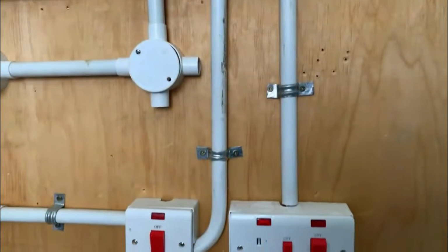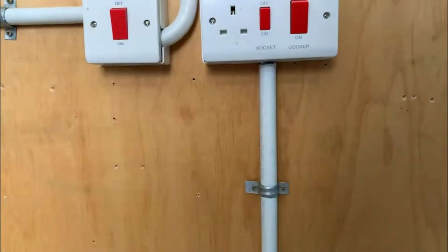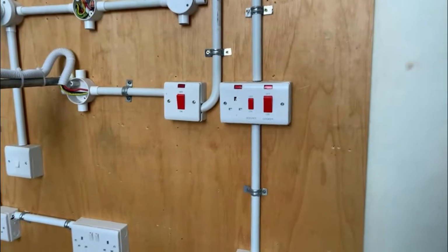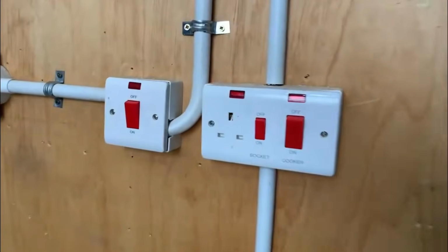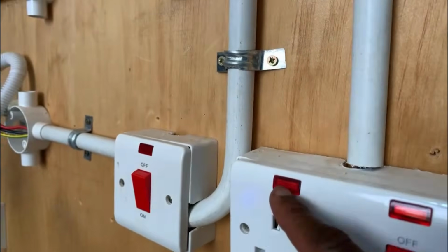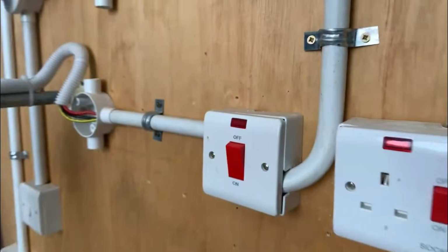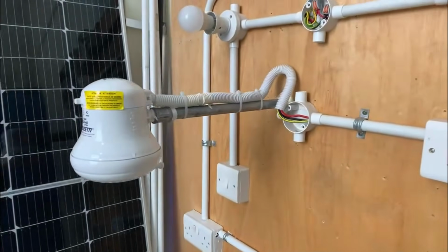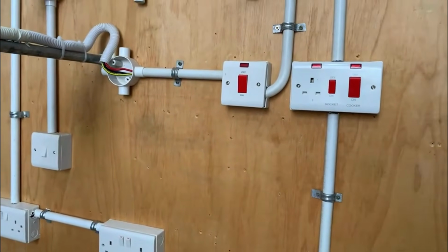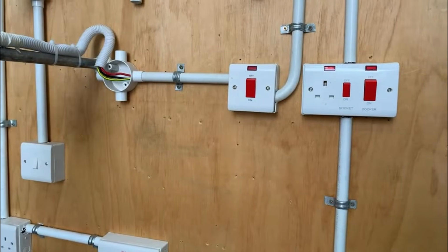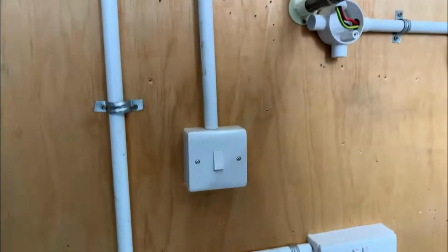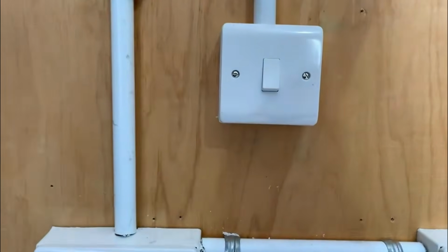These connections serve various circuits, like we have here the cooker. Assuming that the cooker is not receiving sufficient power, there's going to be a problem. Sometimes you'll find that this light here is dim or really flickering, that you can see it with naked eyes. Same as this one for an instant shower head. This is a heater. Heating circuits face a lot of issues, especially if the installation was not done by a qualified person or a careful person who was definitely concerned about tight electrical connections.